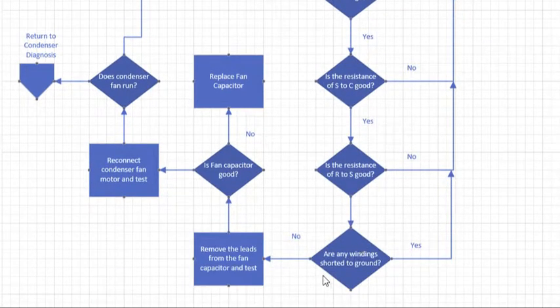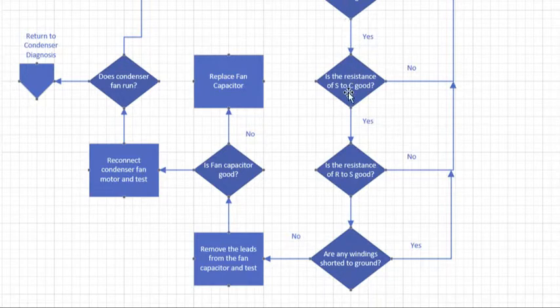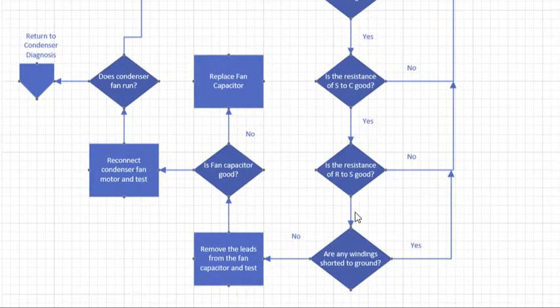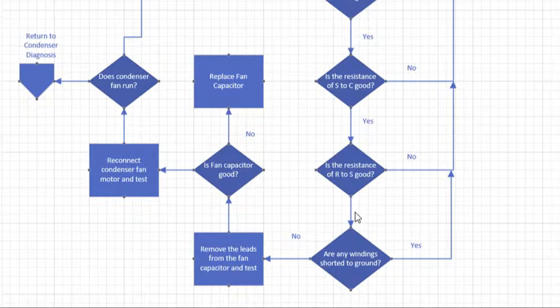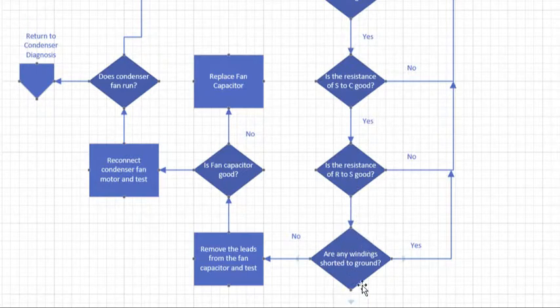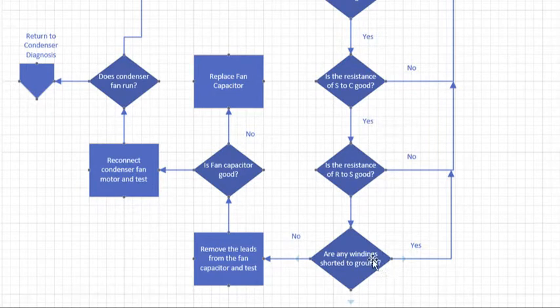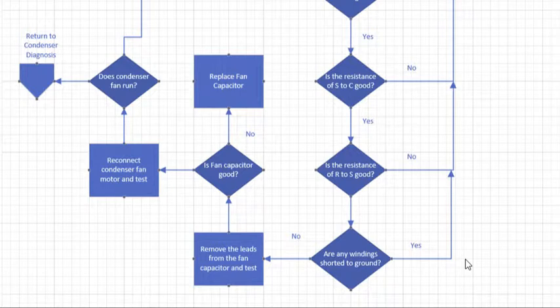The next thing you want to do is take a reading from each of these from the three wires, R, C, and S to ground. Frame, ground, the motor frame itself. Put one lead of your meter on the frame and one lead of the meter on whichever winding you're testing. If any of these windings have a path to ground over or under like 1.2 megohms or 1 megohm, depending on what you're using, that motor shorted to ground, it's going to fail, it's going to start blowing breakers if it hasn't already. Just replace the motor.